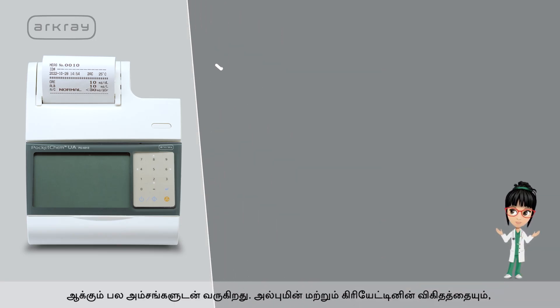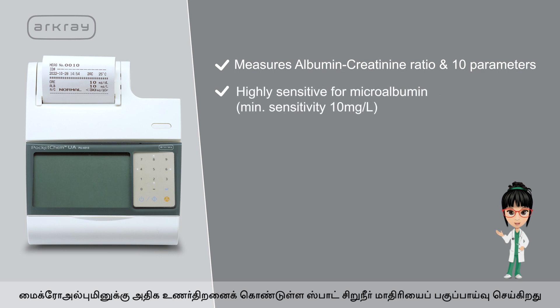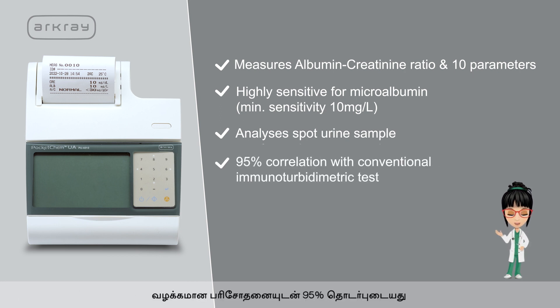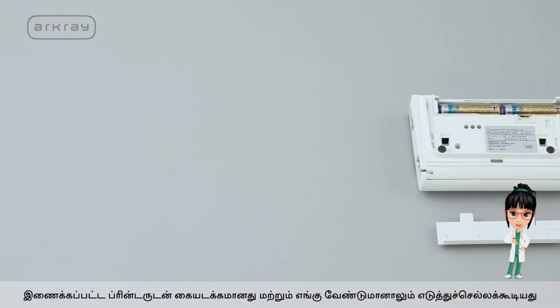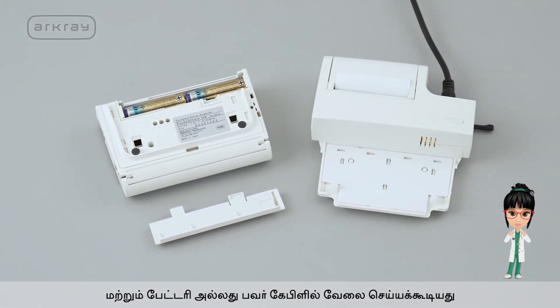PocketChem UA PU-4010 comes with multiple features that make urine analysis simple and quick: measures albumin creatinine ratio and 10 parameters, highly sensitive for microalbumin, analyzes spot urine sample with 95% correlation with conventional test, and is compact and portable with an attached printer that works on battery or power cable.